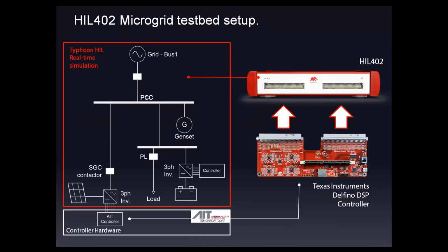You can see here this is a one-line diagram. We have a point of common coupling where our small microgrid is connected, is grid tied with a protective relay device. Here we have a diesel genset model connected to bus number 1. On top of that, we have a three-phase PV inverter that is controlled by an AIT controller. AIT is Austrian Institute of Technologies. This is our partner company, partner institute that we work closely with. They have developed their advanced DSP controller that is running on this Texas Instruments Delfino card, and they were kind enough to share this with us.